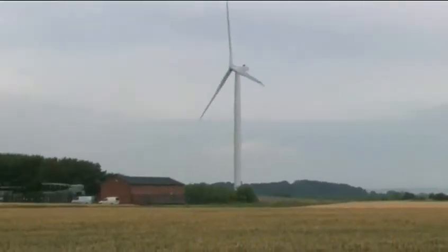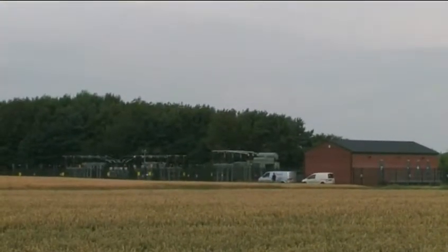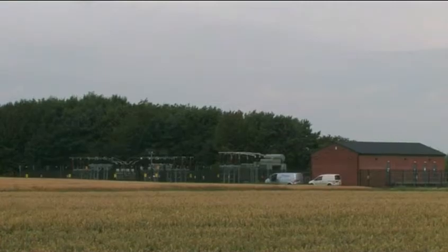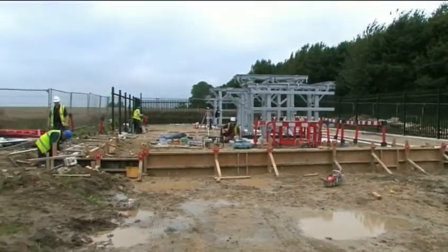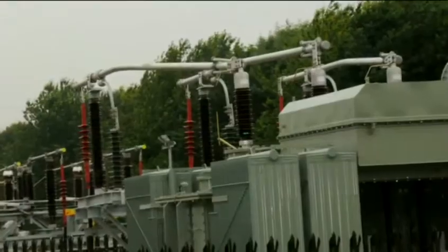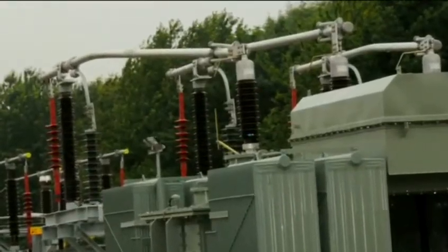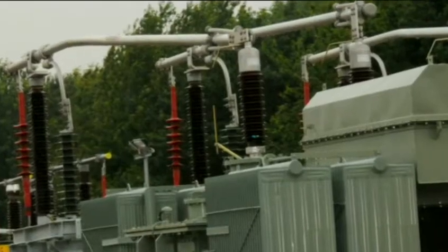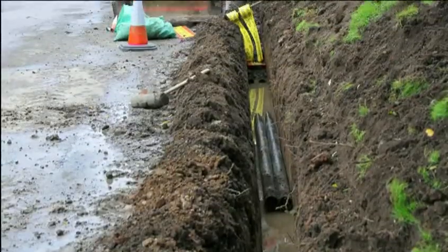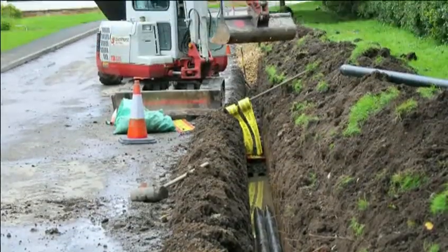The cables converge on the substation, which houses switchgear for the wind farm electrical circuits and a computer control system. From here, the power is fed into the national electricity grid network via a transformer which further steps the voltage up on site from 33,000 volts to 66,000 volts and then travels along 14 kilometres of underground cable.